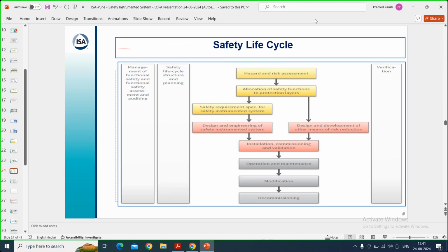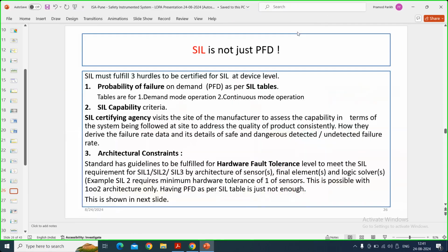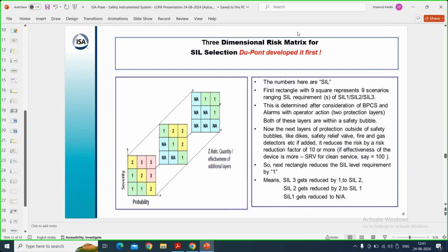What documents are available with you where you have selected your SIL, suppose by the risk method? Let me show you. This is SIL selection by risk matrix. In this slide, if SIL 3 is selected, you add one more layer of protection. Say it is a pressure loop and you add 2 more layers, pressure safety valves. What level will the SIL get reduced to? Your knowledge is very important, and application is equally important. If your safety relief valve is in clean service and of full stroke, full flow size, then probably 2 safety valves can reduce the risk level from SIL 2 to SIL 1.